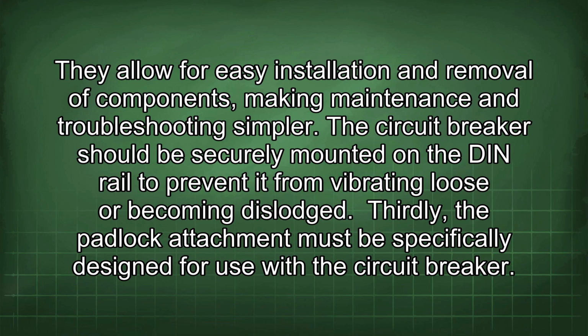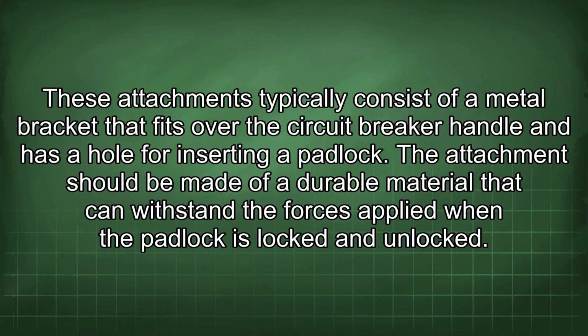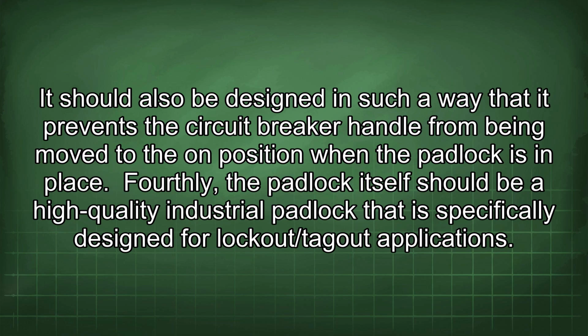Thirdly, the padlock attachment must be specifically designed for use with the circuit breaker. These attachments typically consist of a metal bracket that fits over the circuit breaker handle and has a hole for inserting a padlock. The attachment should be made of a durable material that can withstand the forces applied when the padlock is locked and unlocked. It should also be designed in such a way that it prevents the circuit breaker handle from being moved to the on position when the padlock is in place.